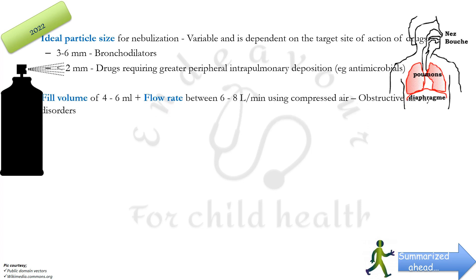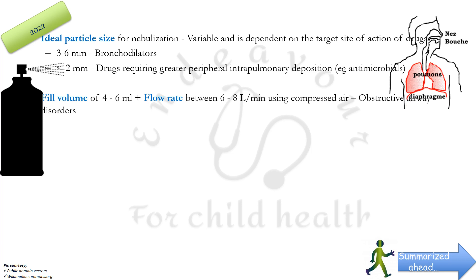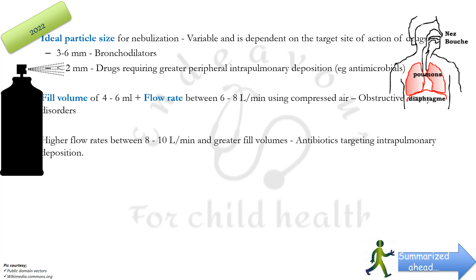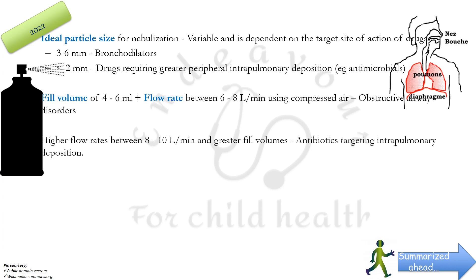A fill volume of the nebulization chamber of 4 to 6 ml and a flow rate of 6 to 8 liters per minute using compressed air is primarily used for obstructive airway disorders like bronchial asthma. Higher flow rates of up to 8 to 10 liters per minute and even greater fill volumes are used for drugs meant for intrapulmonary deposition — those which need to be deposited in the alveoli and not the bronchioles.